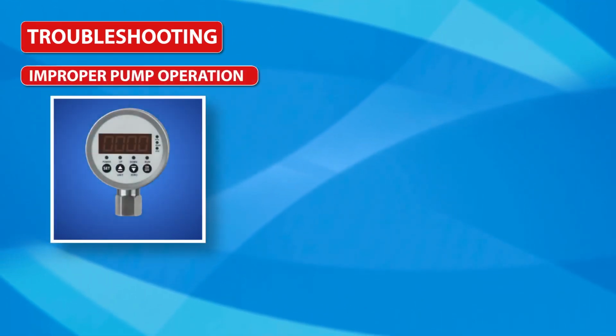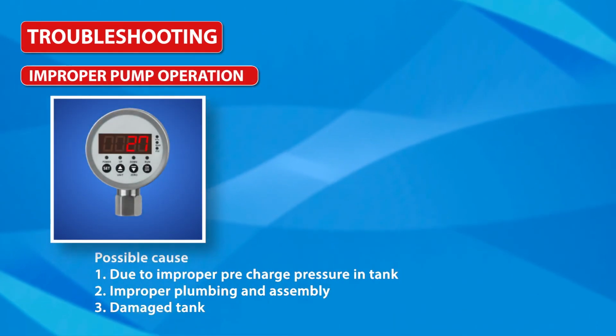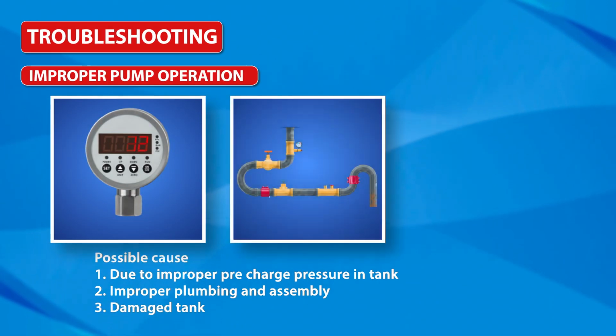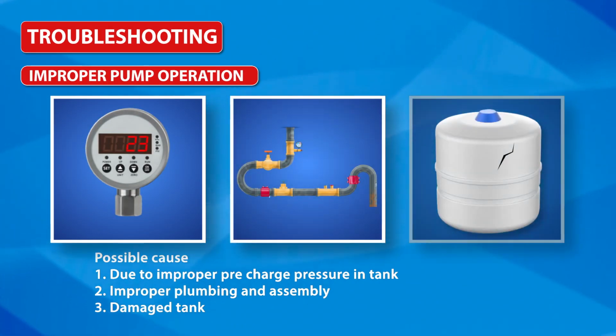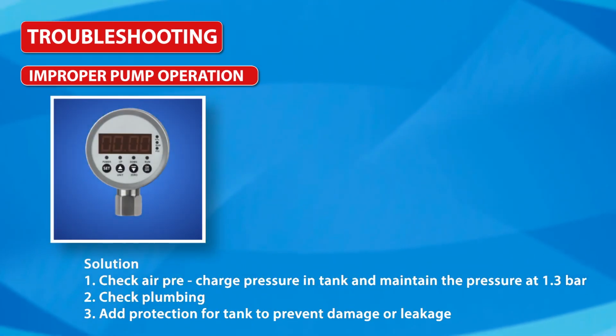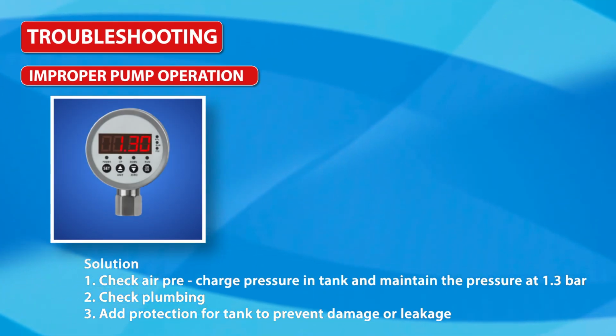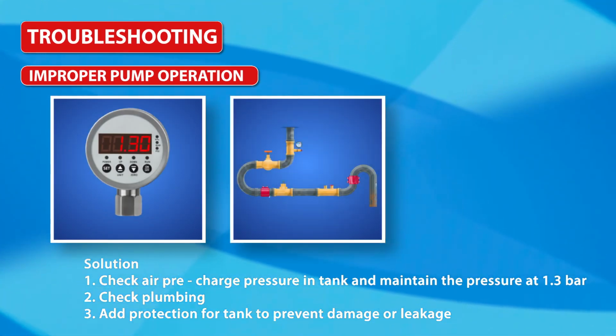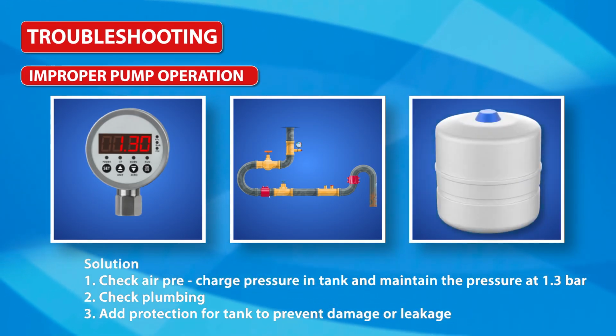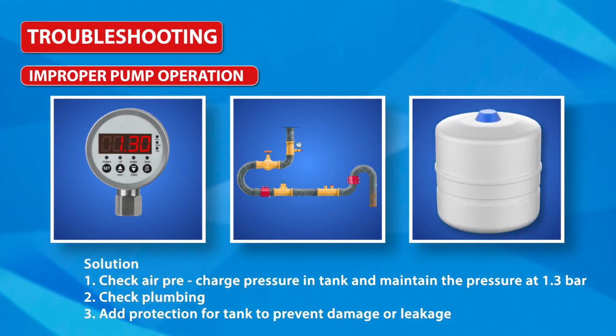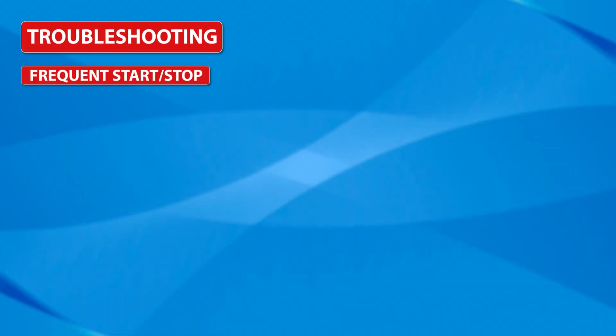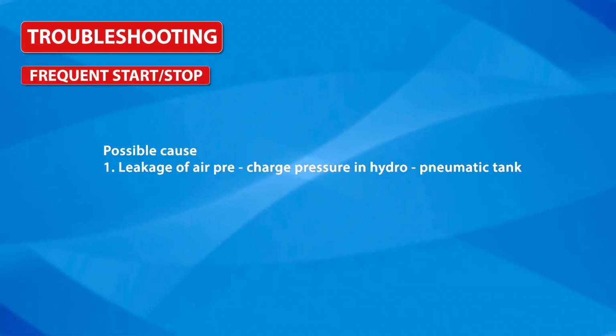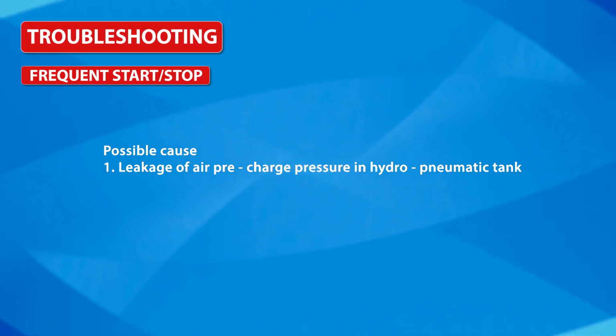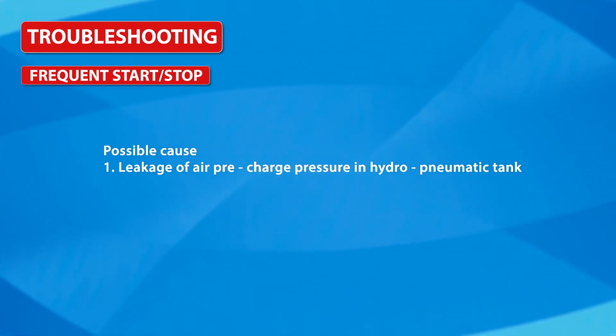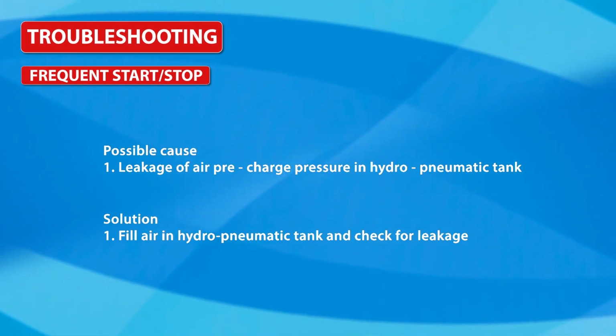Improper pump operation. Possible cause: first, improper pre-charge pressure in the tank. Second, improper plumbing and assembly. Third, damaged tank. Solution: first, check air pre-charge pressure in the tank and maintain the pressure at 1.3 bar. Second, check plumbing. Third, add protection for the tank to prevent damage or leakage. Frequent start or stop. Possible cause: leakage of air pre-charge pressure in the hydro-pneumatic tank. Solution: fill air in the hydro-pneumatic tank and check for leakage.